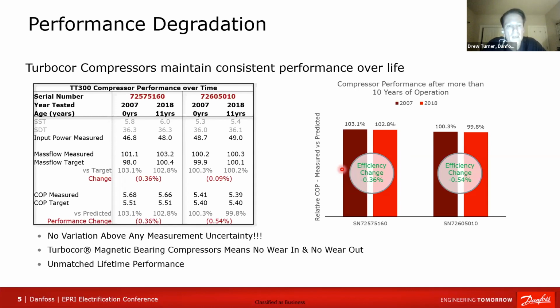So if you listen to a screw compressor about 5 years after it's installed, it's quieter. The reason for that is that the metal-to-metal contact is worn down, and what that is, is loss. So it becomes quieter but it also drives losses. If you wear down that metal-to-metal contact over time, you drive losses from the high side to the low side. And so with no contact and with no oil in the system, which is the other main factor driving performance degradation, if you eliminate both of those, then you should have no performance degradation over time.